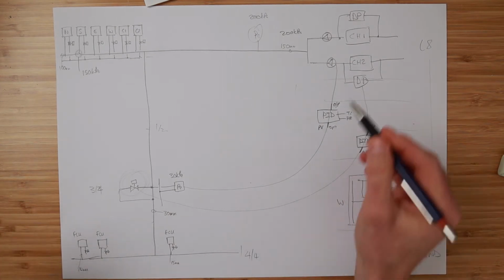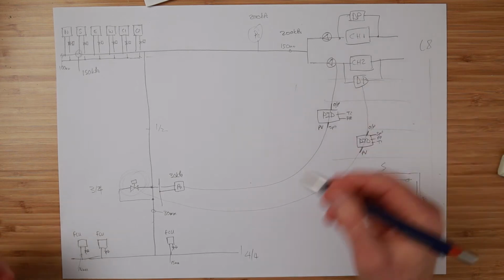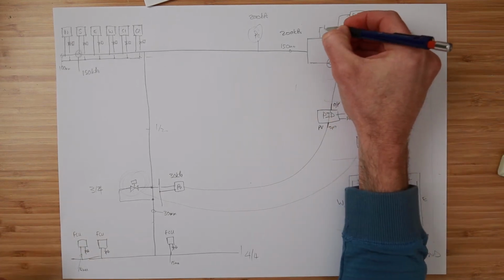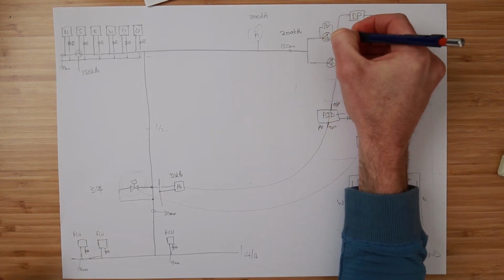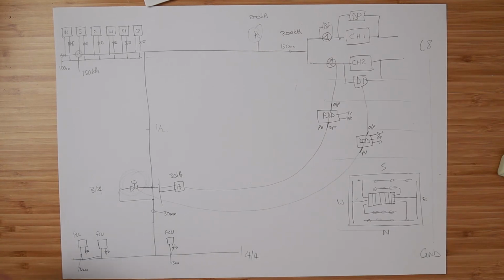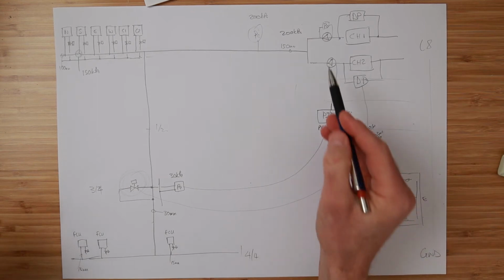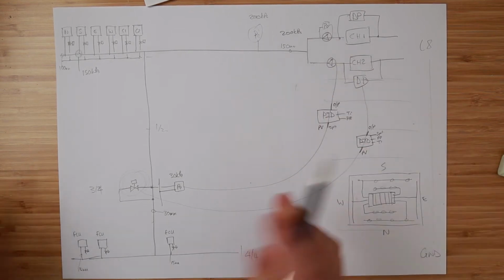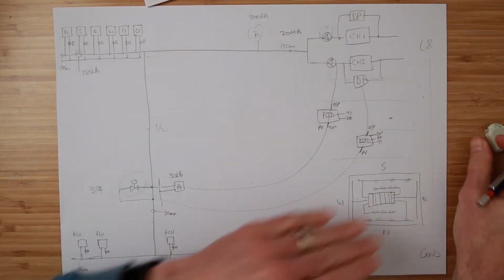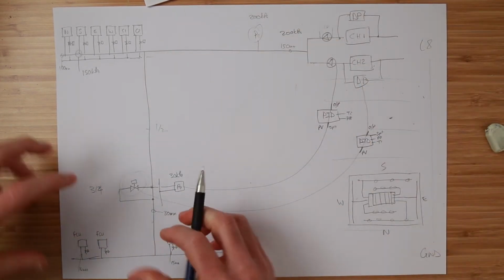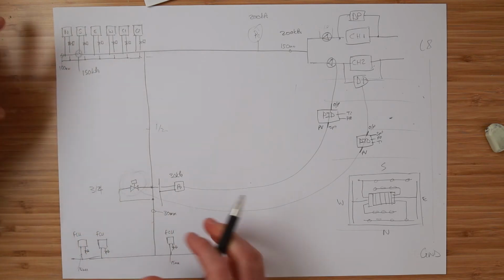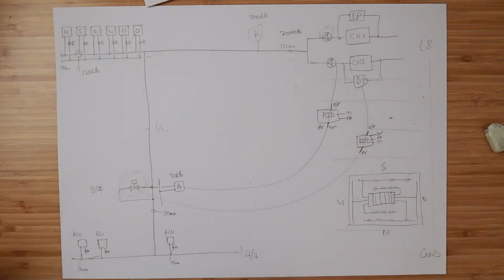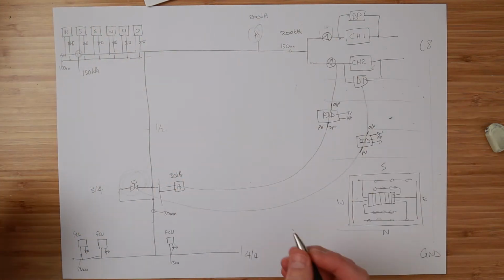I've actually seen packaged pump sets come to site with the pressure transmitter actually installed off the packaged pump set as a packaged system. This was in the UK a very long time ago. And I didn't actually check it, but maybe it works. Let's just forget about that for a minute. But what I'm trying to say to you is, as things are closing off in the field and the pressure's changing, that pressure does sort of make its way through the system. You do detect it and it does slow down.